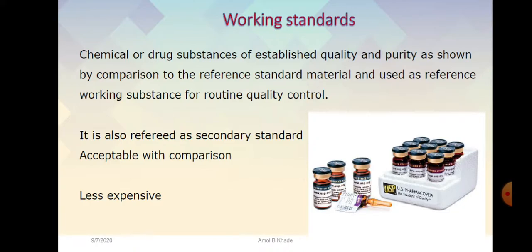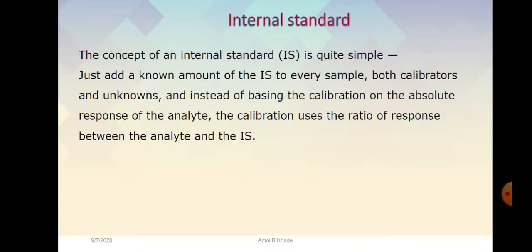It is also referred to as a secondary standard, and it is acceptable with comparison. So the working standard needs to be compared with the reference standard, and only then can you use the working standard, whereas the reference standard doesn't require any comparison because it is already considered a gold standard. Compared to reference standards, working standards are less expensive and usually available in a larger volume or larger quantity.